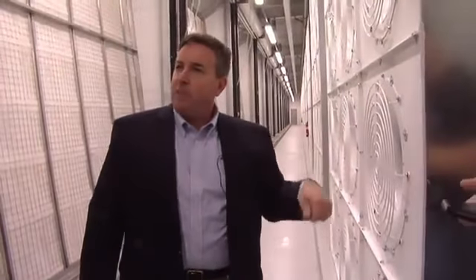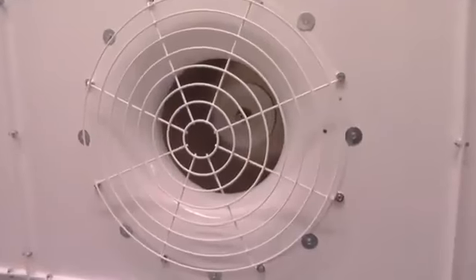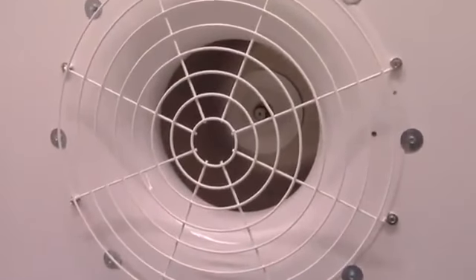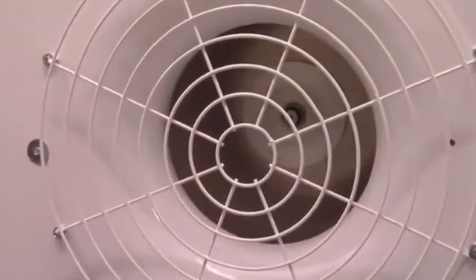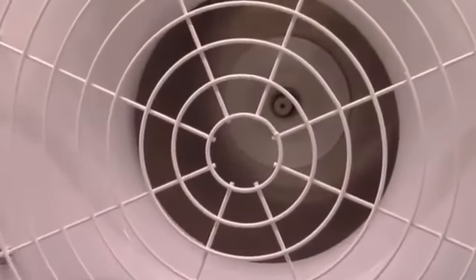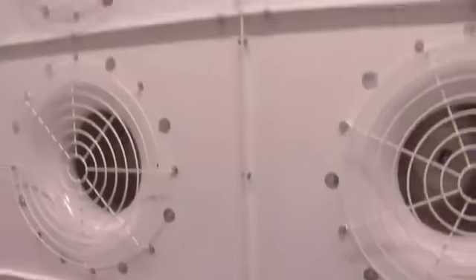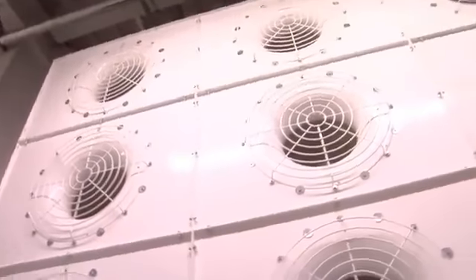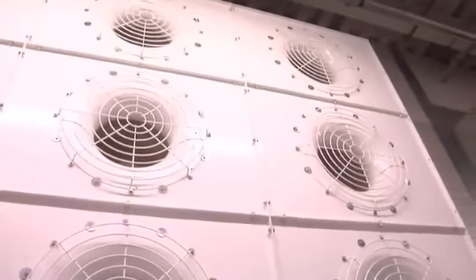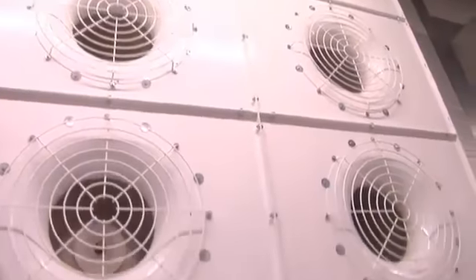The fans will speed up or slow down depending on the amount of air that needs to get down into the space. Little fans in servers aren't terribly efficient. Big fans like these are tremendously efficient. So the way we engineer the open compute hardware is we have it such that by pressurizing the space down below, we basically suppress the fan speed in the servers themselves.